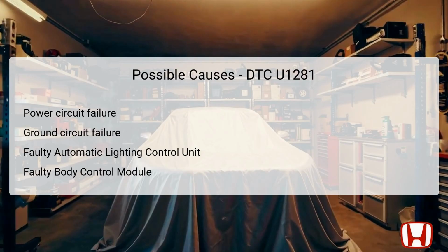The first possible cause is a failure in the power circuit supplying the MICU. This circuit is essential for the module's operation. If the power is interrupted or insufficient, the communication with the Automatic Lighting Control Unit will be compromised. The second cause could be a ground circuit failure, which is equally crucial. A proper ground connection is necessary for the electrical systems to function optimally. Without it, the return path is interrupted, leading to communication issues.